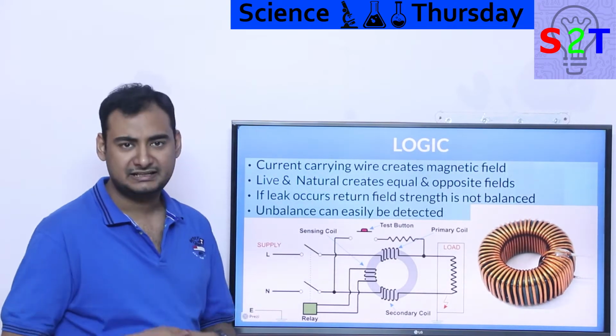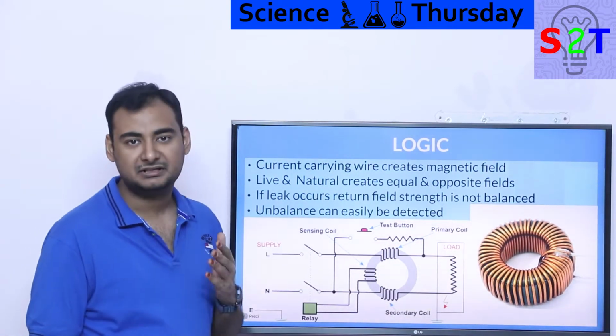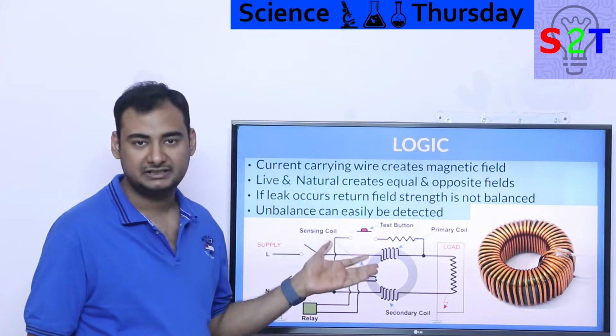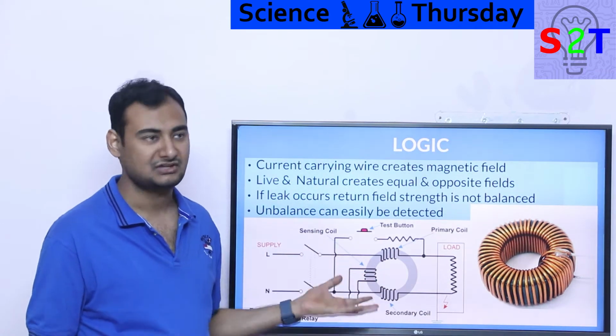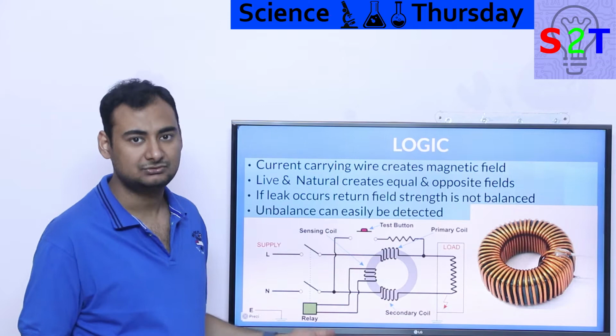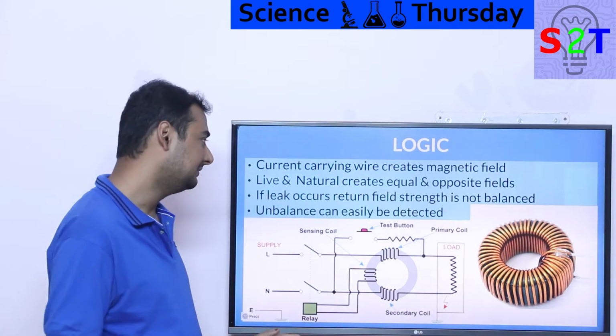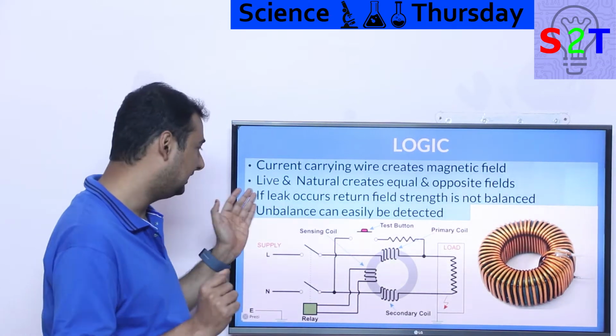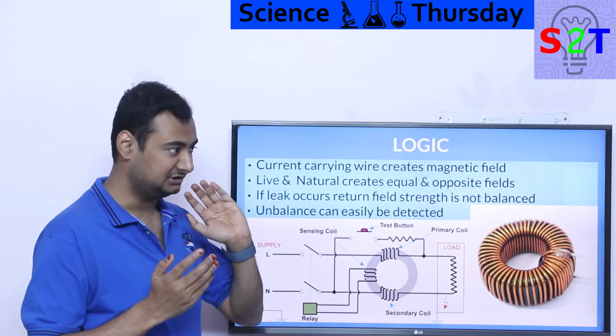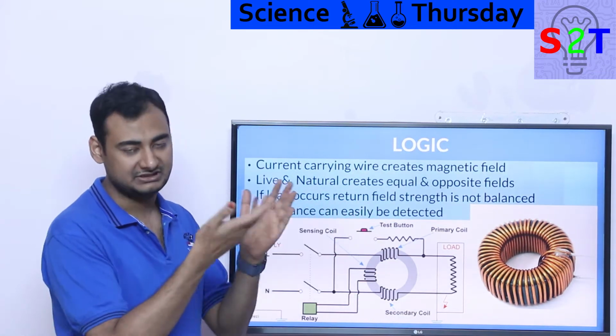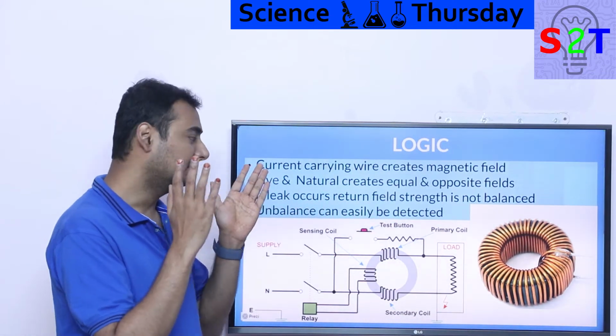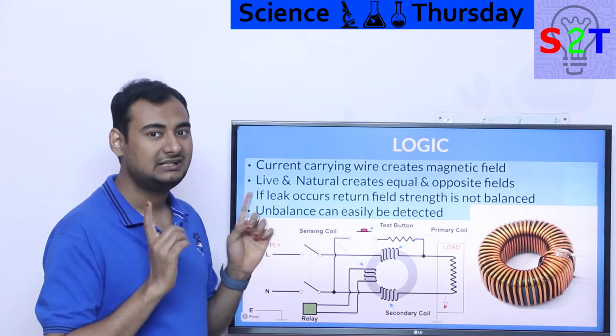Well, the logic is inherently very simple. If you have a current carrying conductor, it creates a magnetic field. That's simple. That's how a transformer works. That's how almost everything that we do works. So inherently, it's a simple thing. However, here's the interesting part. If you have live and you have neutral, basically you send electricity, you receive electricity, as in the electron flow is reversed. Both of them will create an equal and opposite field.